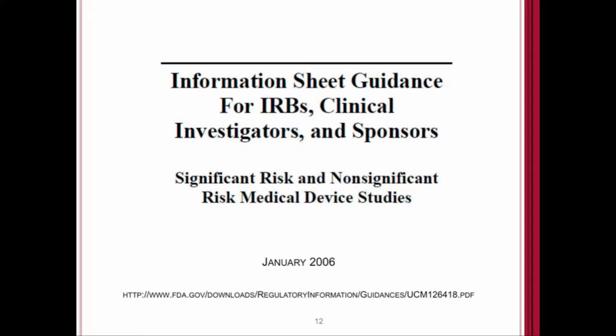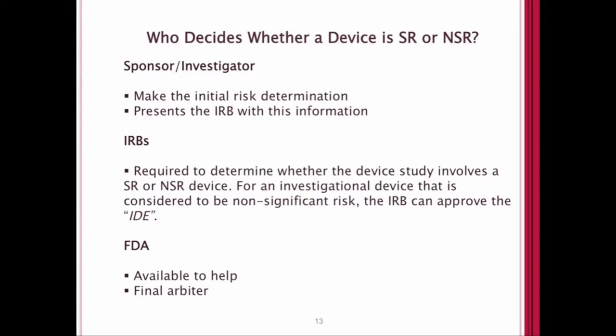In January 2006, the FDA put out a guidance document that is one of the primary aspects of moving forward with a medical device in the development process — specifically whether you need clinical trials and if you need an investigational device exemption application approved by the FDA before you can move forward with clinical studies. The title of this document is 'Significant Risk and Non-Significant Risk Medical Device Studies.' FDA walks you through decision trees and gives examples of things that are significant and non-significant risk, because the risk classification determines how you move forward with clinical studies.